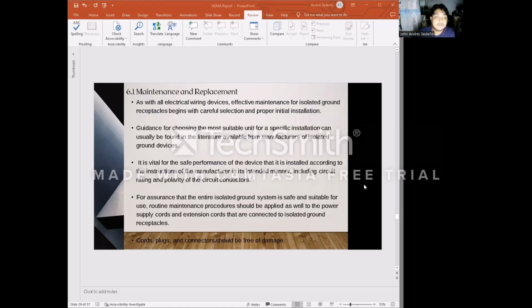It is vital for the safe performance of the device that it is installed according to the instructions of the manufacturer in its intended manner, including circuit rating and polarity of the circuit conductor, for assurance that the entire isolated ground system is safe and suitable for use. Routine maintenance procedures should be applied, as well as to power supply cords and extension cords that are connected to the isolated ground receptacle. Cords, plugs, and connectors should be free of damage.